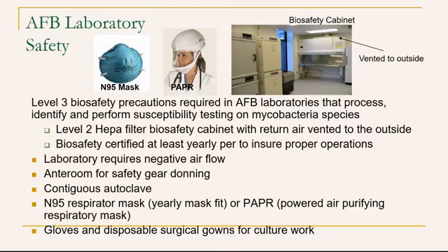You must have these biosafety cabinets certified at least yearly to ensure that you have proper operations and your lab is safe. The laboratory requires negative airflow. You need an ante-room for entry for your safe gear donning and doffing. Contiguous autoclave. N95 respirator masks must be worn with a yearly mask fit test.